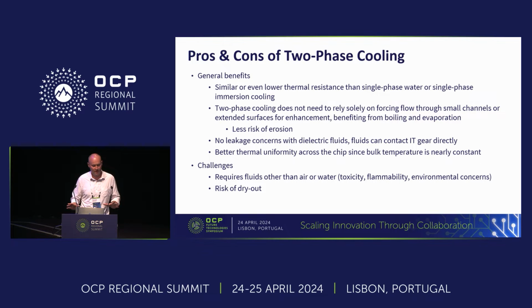Now, general pros and cons of two-phase cooling. Because of the boiling mechanism, we tend to get thermal resistances that are the same, if not lower, than single-phase water. We don't rely on forcing flow through small channels; we're relying on the boiling mechanism. So even some filtering requirements and other concerns become less important with two-phase cooling.